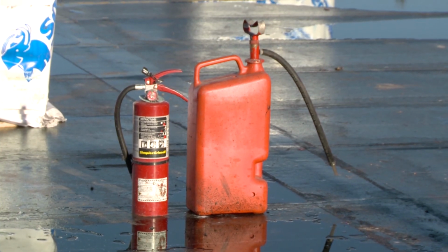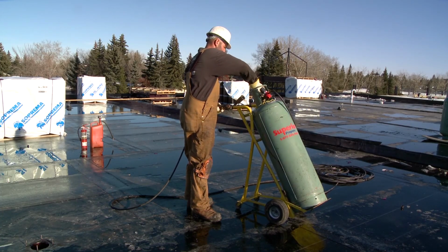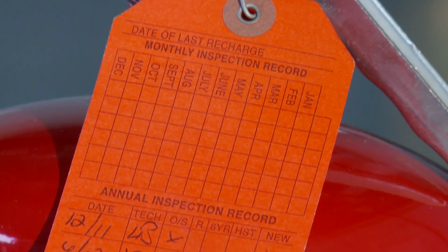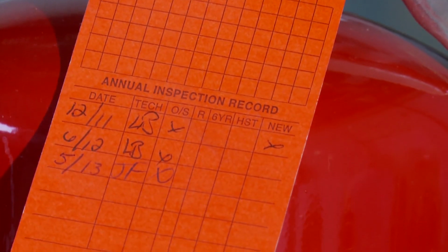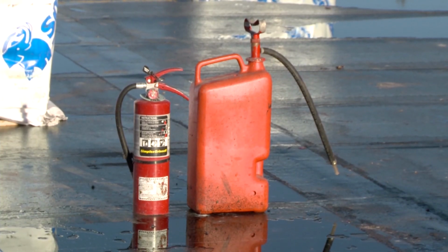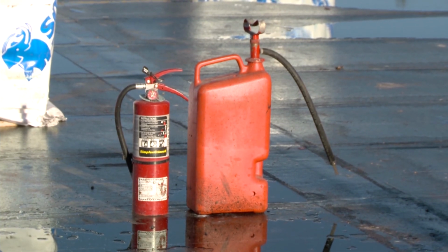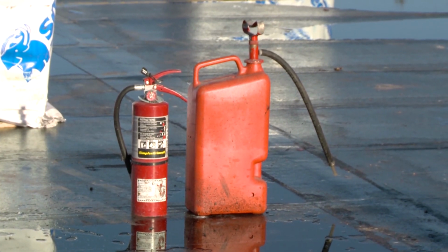Operable water and ABC chemical-type fire extinguishers shall be placed in the work area. Check that the extinguisher has the correct inspection tag and that the pin cap or seal and handle are secured. Use water extinguishers for fiberboard fires. Do not use water on asphalt fires. Use ABC-type extinguishers for flammable liquids, primers, and asphalt fires.